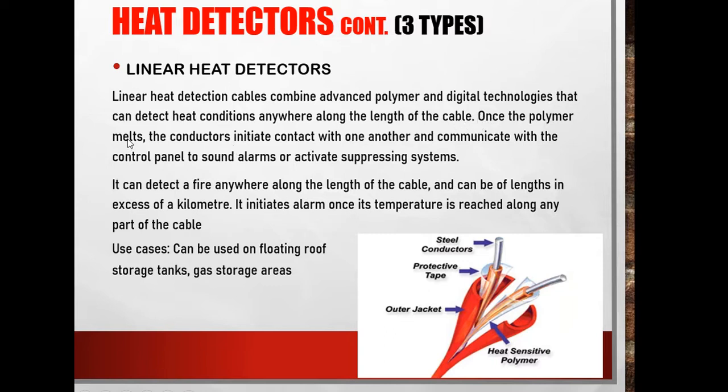Once the polymer melts, the conductors make contact with one another and communicate with the control panel to sound alarms or activate suppressing systems. So it could be used for, let's say, up to a kilometer distance. Anywhere on the entire cable that heat reaches a certain temperature, it automatically triggers an alarm. That is very useful because it's not just on one spot. It's cost effective.